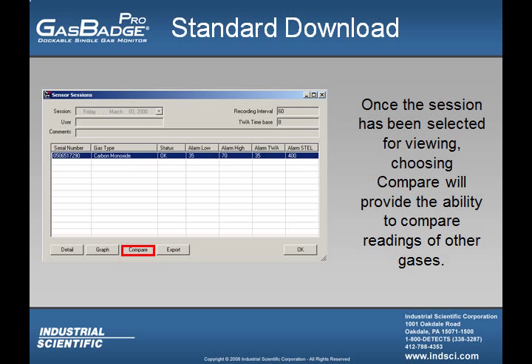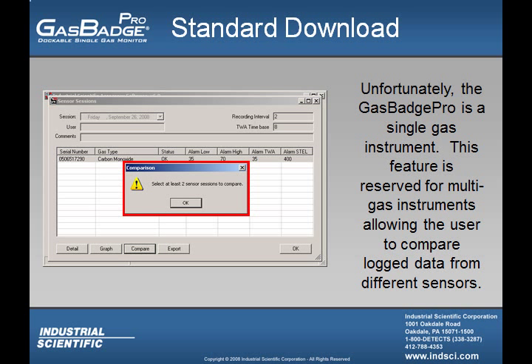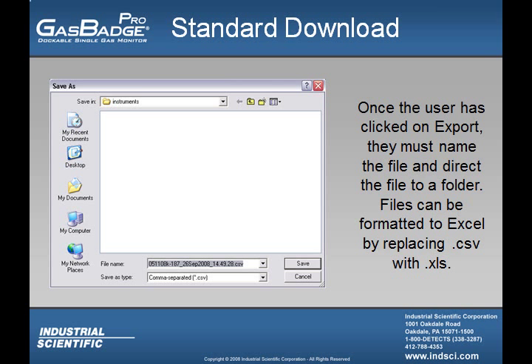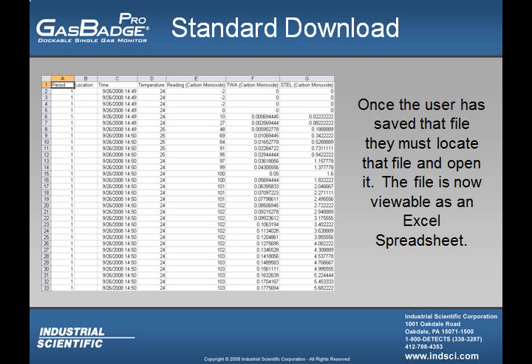If the user wanted to compare two or more sensors, they can click on that tab. However, it's important to know that the Gas Badge Pro is a single gas instrument — this feature is reserved for multi-gas instruments, which allow the user to compare logged data from different sensors. Finally, if the user wants to save the session's data into a different file format, they can click on Export, name the file, and direct it to a folder. Data logging sessions can be formatted for Excel by replacing the .csv extension with .xls. Once saved, the user can locate the file, open it, and view that session as an Excel spreadsheet.